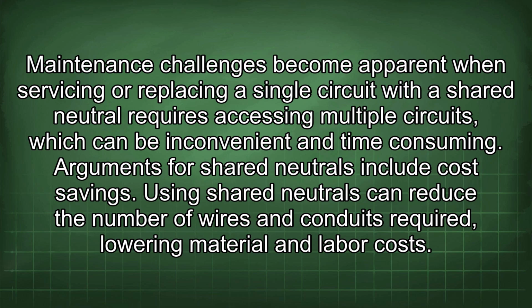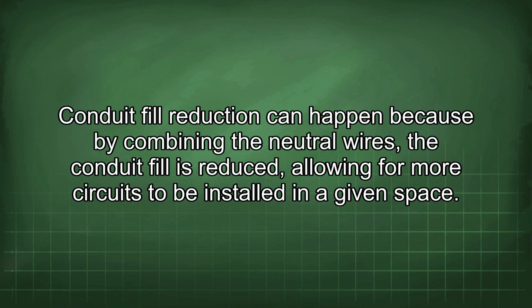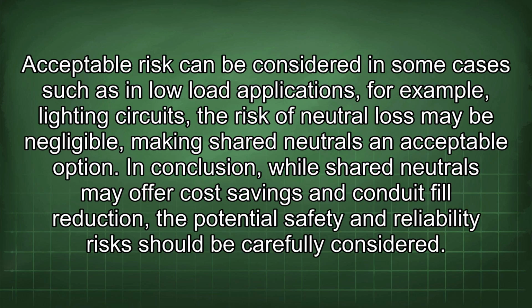Arguments for shared neutrals include cost savings. Using shared neutrals can reduce the number of wires and conduits required, lowering material and labor costs. Conduit fill reduction can happen because by combining the neutral wires, the conduit fill is reduced, allowing for more circuits to be installed in a given space. Acceptable risk can be considered in some cases such as in low-load applications, for example, lighting circuits. The risk of neutral loss may be negligible, making shared neutrals an acceptable option.